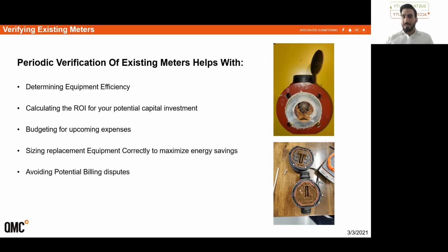And as the meter was extracted to see what's wrong with it, as you can see, there's a lot of buildup within that water meter. Also, the picture below that is a BTU meter. That's the inside view of a BTU meter, and this is another challenge within the hydronic systems and in multi-residential buildings. More often than not, water quality treatment within the property is not great. It's either manual or it's not being maintained and tested as it should.